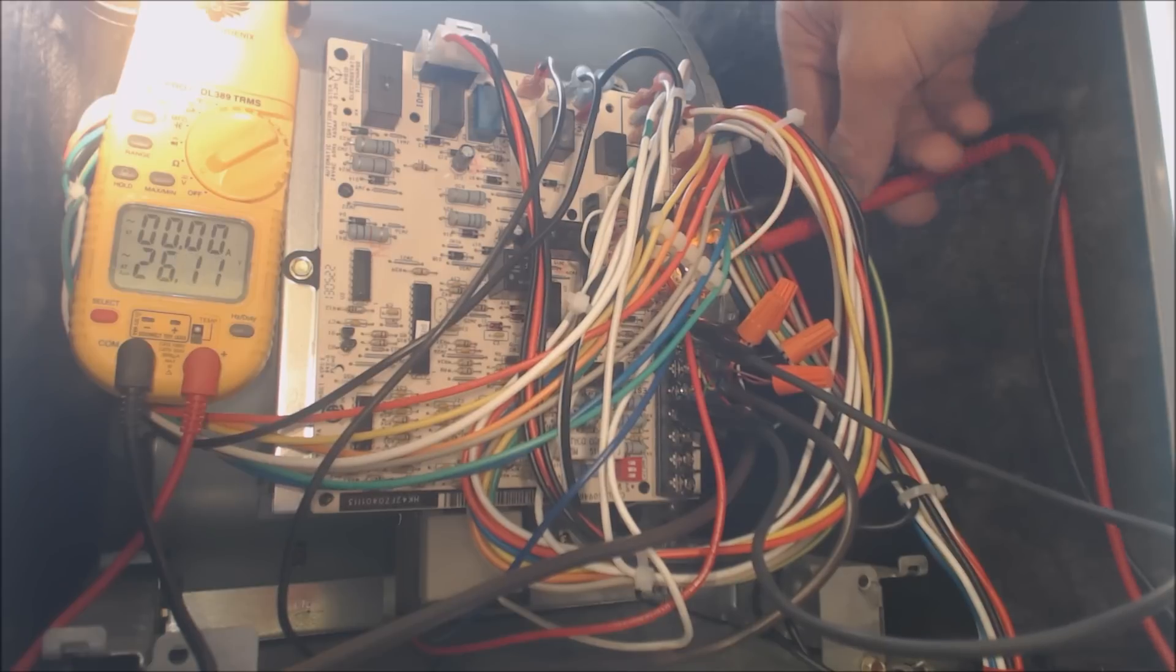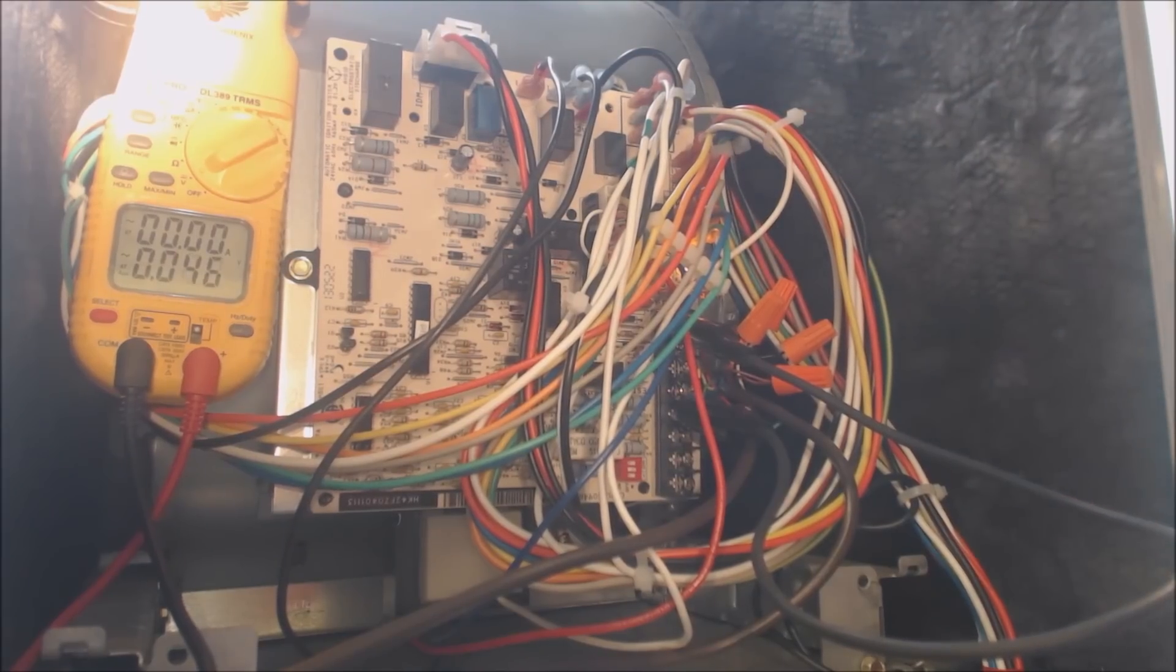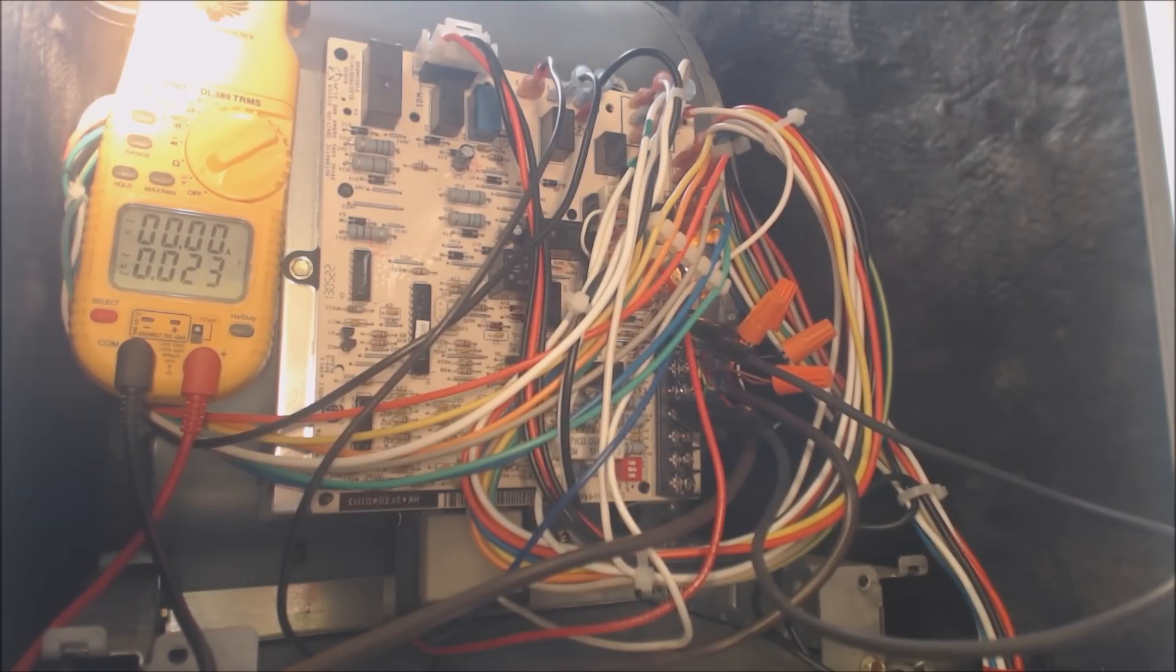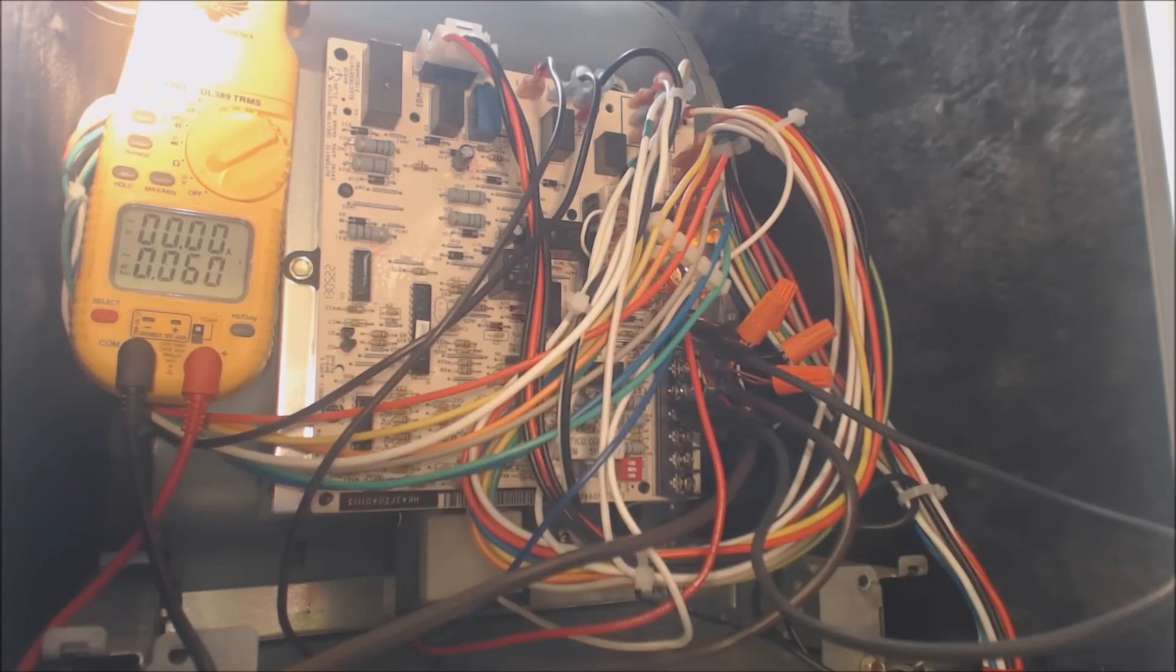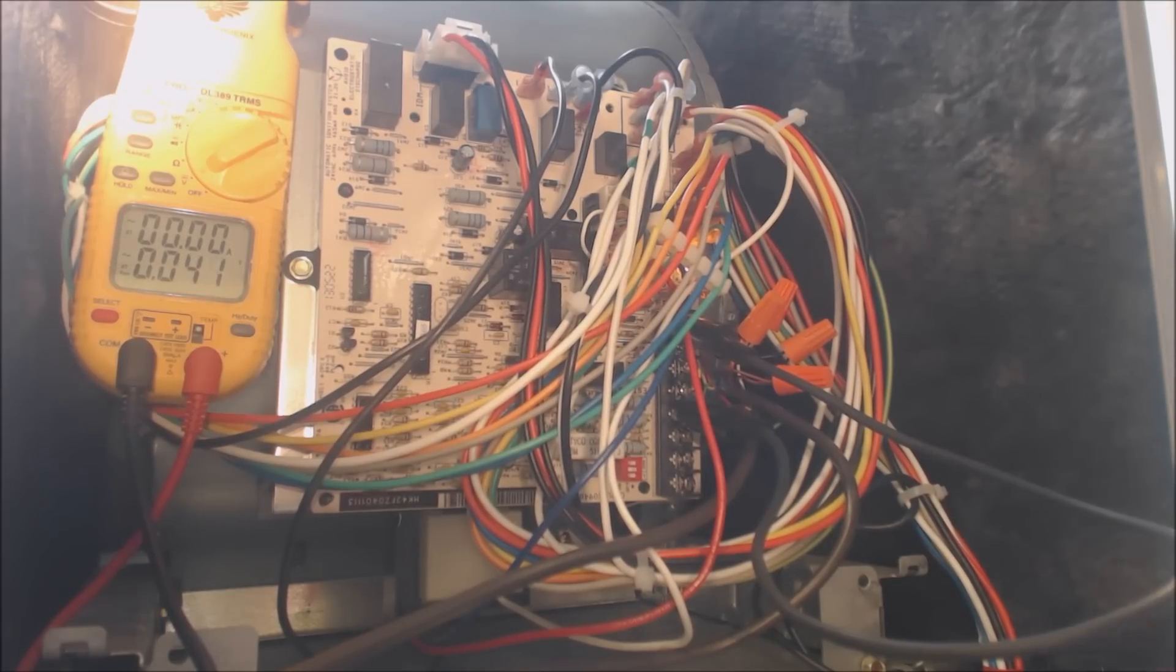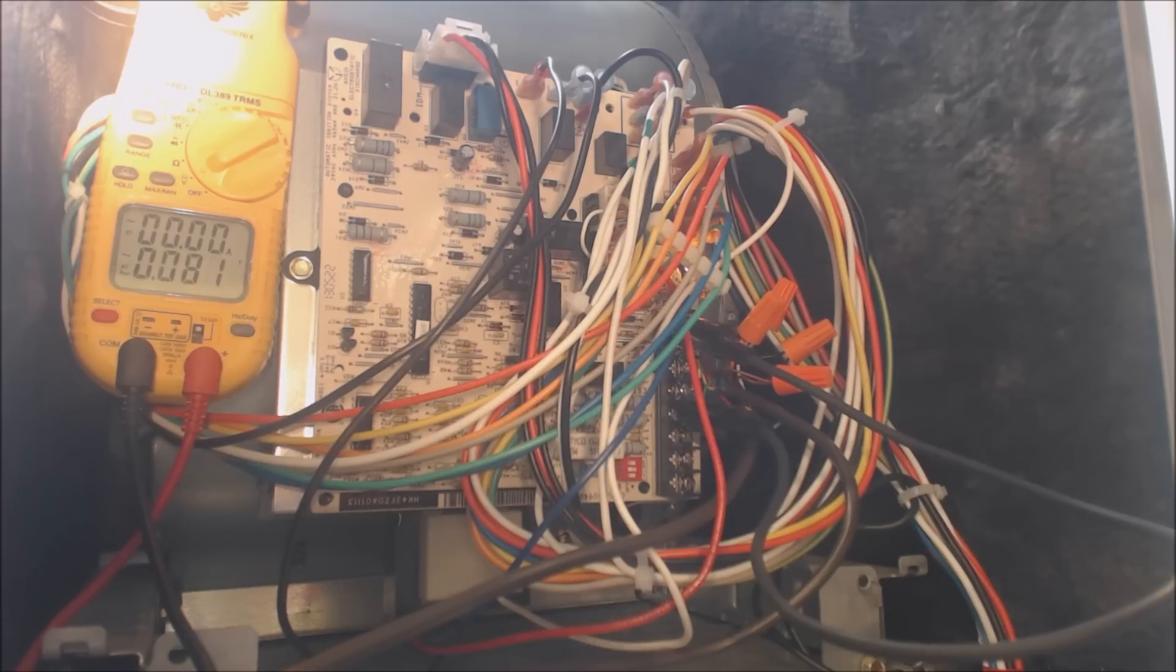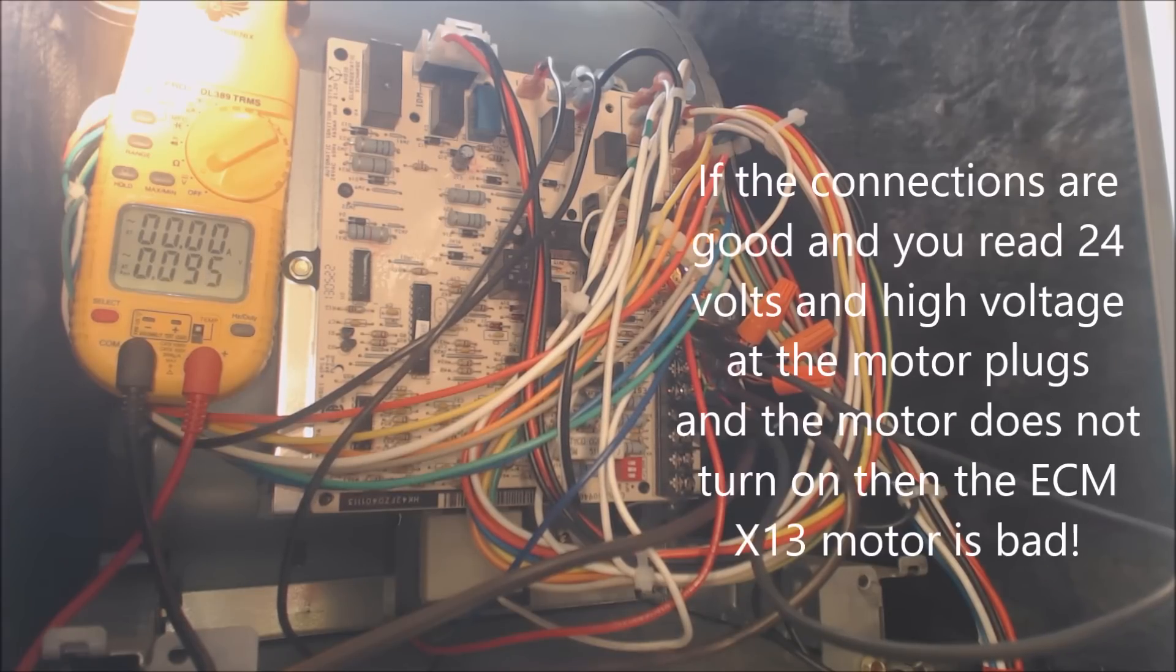So that blower motor is good. So that could have been a loose wire or something like that. So that X13 motor is good. We checked for the 24 volt signal. We know it has a 24 volt signal. We just heard it click on the control board because we have our red and green wires jumped, our R and G terminals. So that ECM motor is good.